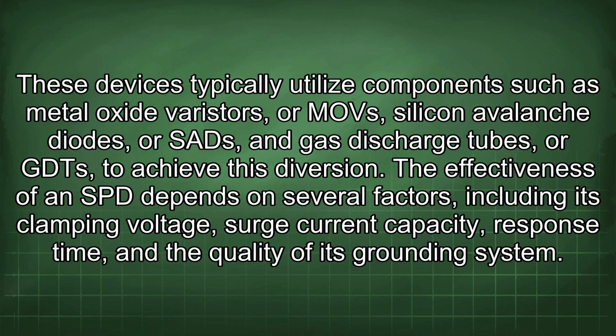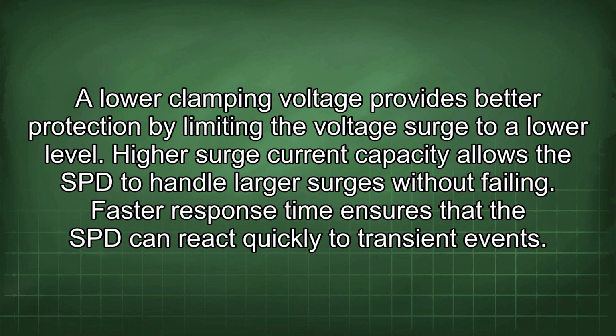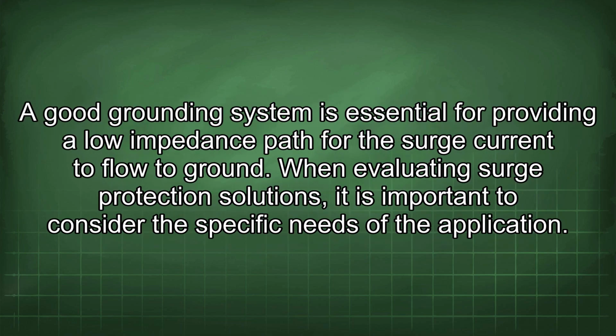The effectiveness of an SPD depends on several factors, including its clamping voltage, surge current capacity, response time, and the quality of its grounding system. A lower clamping voltage provides better protection by limiting the voltage surge to a lower level. Higher surge current capacity allows the SPD to handle larger surges without failing. Faster response time ensures that the SPD can react quickly to transient events. A good grounding system is essential for providing a low impedance path for the surge current to flow to ground.